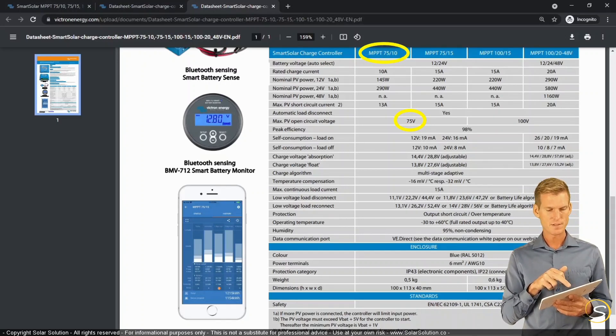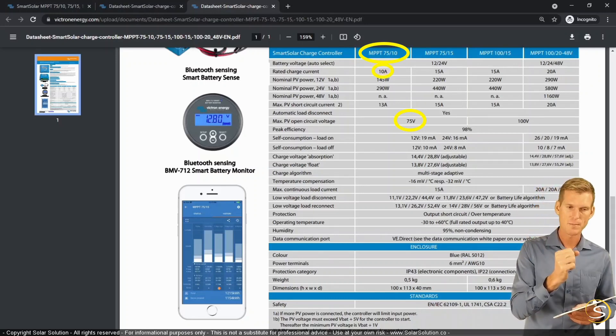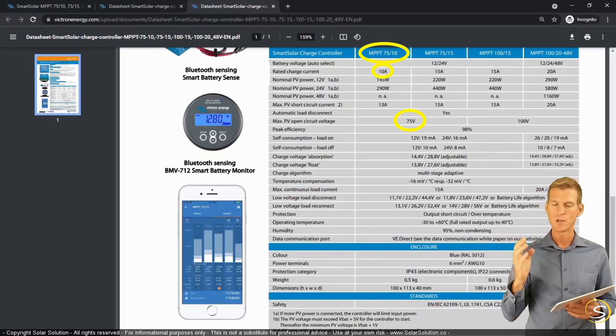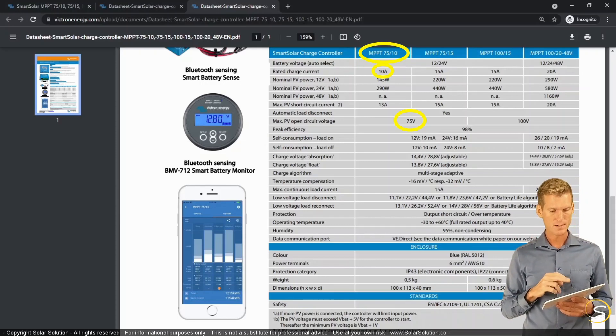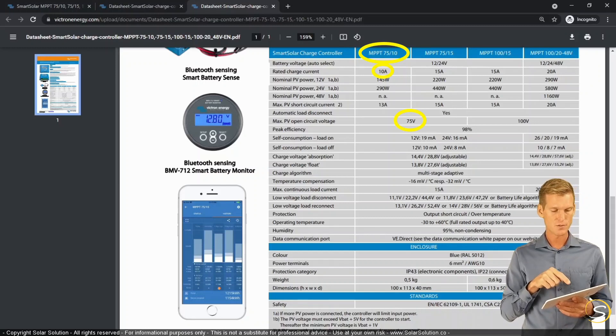Now you understand where the 75 and the 10 comes from. So 75 is the maximum open circuit voltage of your PV array. And 10 amps is the maximum amount of amps from the solar charge controller towards the load, towards the battery.